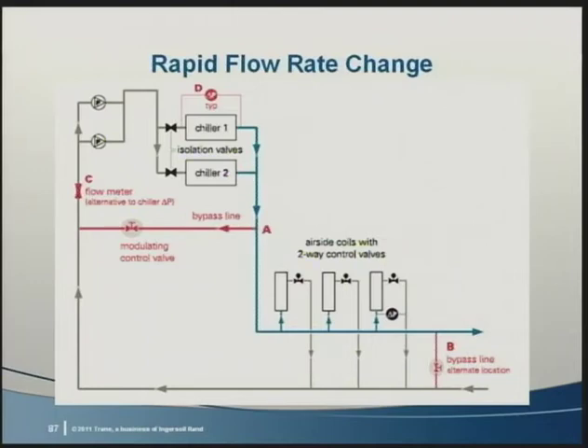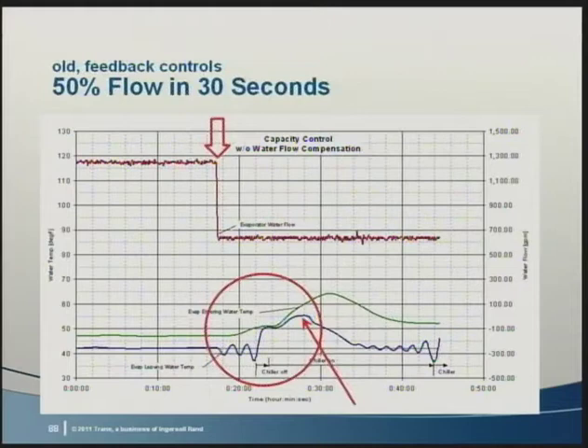The first chiller is operating and at some point becomes fully loaded and can no longer meet the temperature requirements. At that time, the isolation valve on chiller 2 is opened. If it opens quickly enough, the flow rate through the operating chiller drops by 50% very rapidly. Let's see how the controls react in this situation, which is a very rapid flow rate change. Okay, so here we show what will happen to a chiller with a 15 to 20-year-old unit controller when we change the flow. This is similar to the disturbance you might see when another chiller comes online, like I just described. In this example, we have decreased the flow by 50% over 30 seconds.